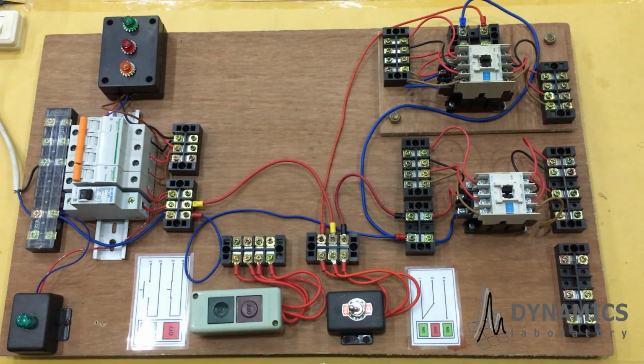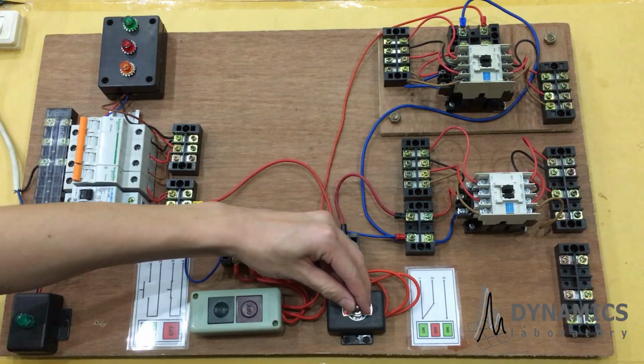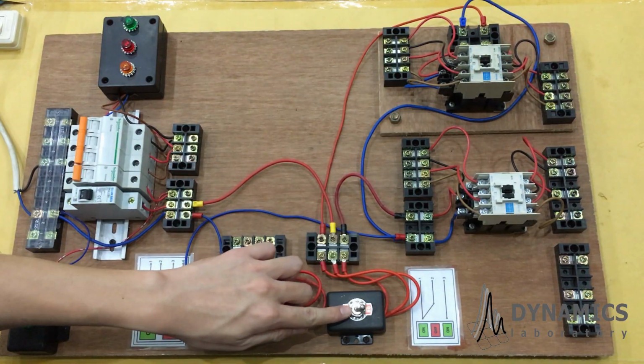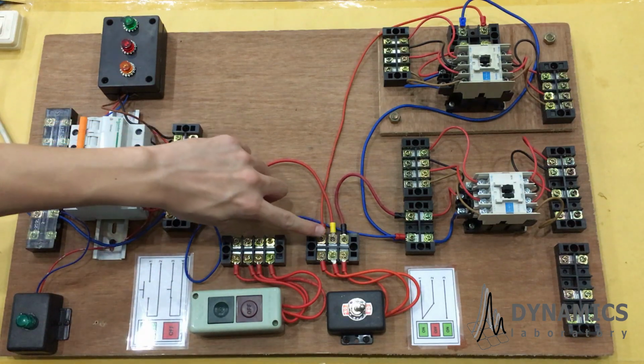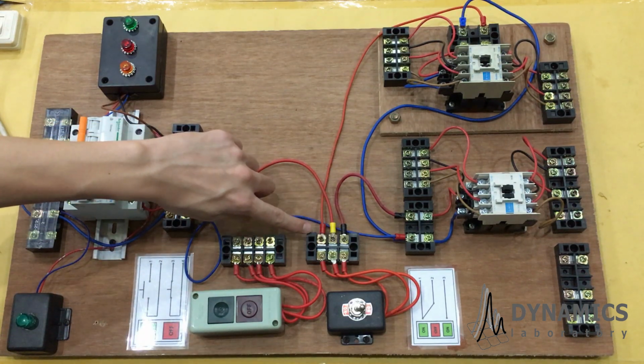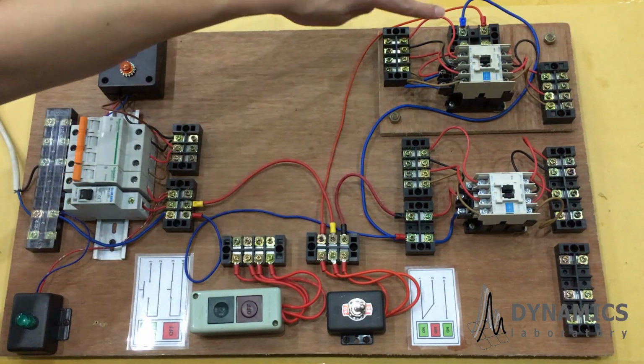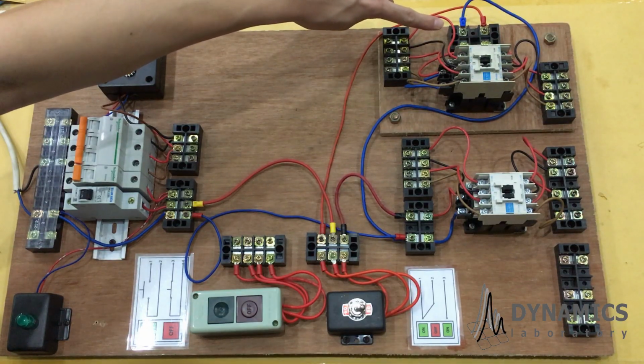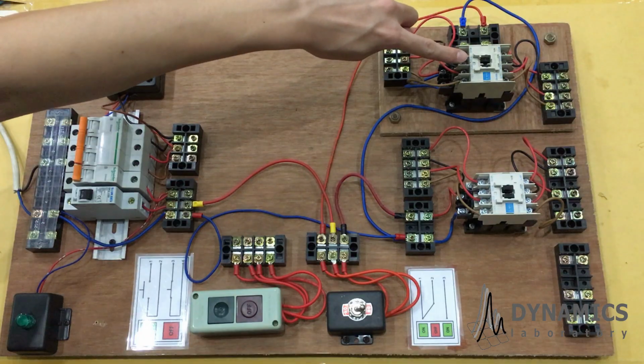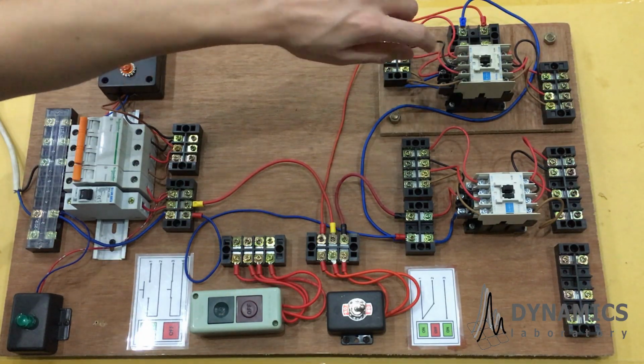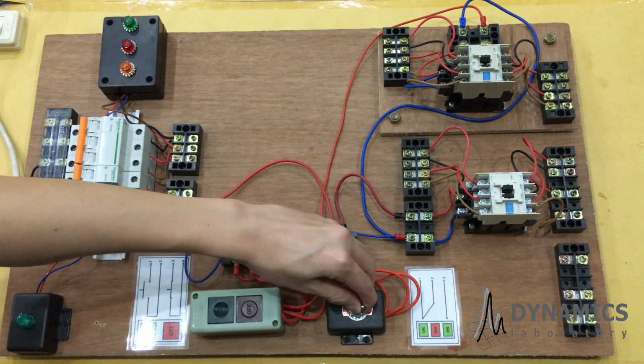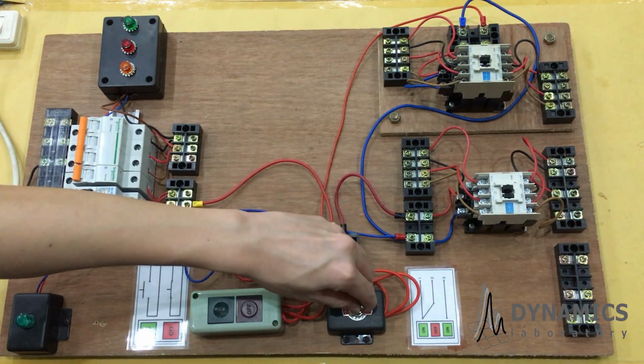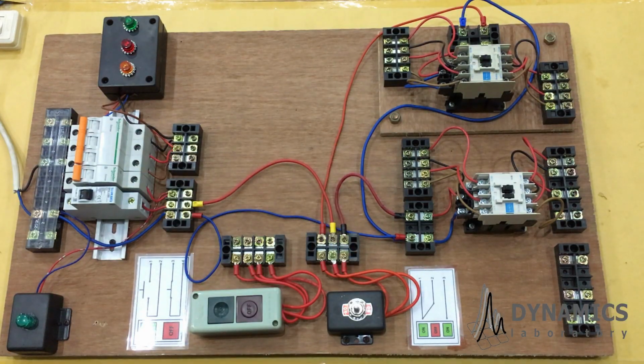Lever in left position. Right now, try the right position. Lever to the right, which means middle leg of the switch is connected to the left leg of the switch, which means coil contactor 2 is energized and makes the contactor on. Off, on, off, and on. That's why when you use switch control circuit, you can directly control two contactors.